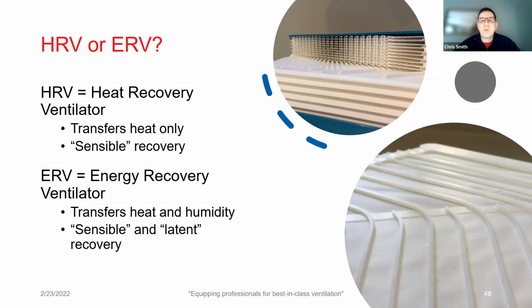In these pictures, we're looking at some examples of two different types of plates in these fixed plate recovery devices. The top is more rigid plates in a heat recovery ventilator. The bottom shows a more membrane-based plate. It's a vapor permeable membrane, so that the humidity as well as the heat can transfer through the membrane. The differences in structure accomplish different things. They also require different manufacturing processes, and they result in slightly different recovery profiles.